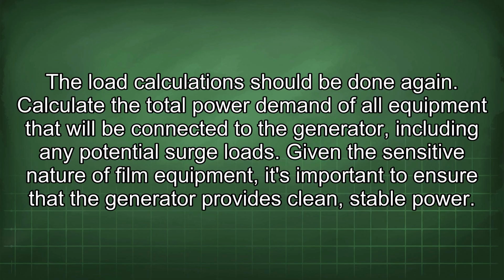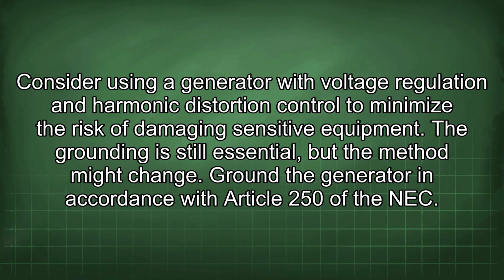Calculate the total power demand of all equipment that will be connected to the generator, including any potential surge loads. Given the sensitive nature of film equipment, it's important to ensure that the generator provides clean, stable power. Consider using a generator with voltage regulation and harmonic distortion control to minimize the risk of damaging sensitive equipment.